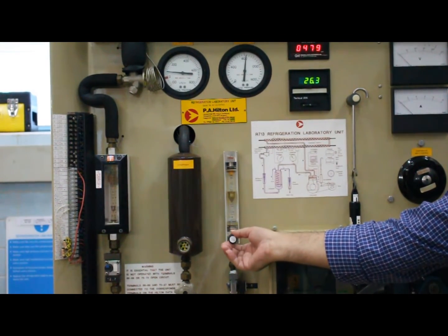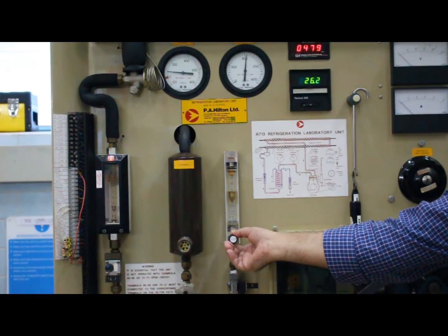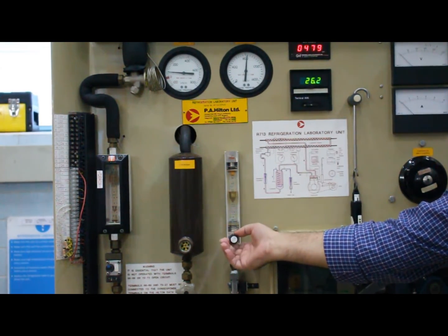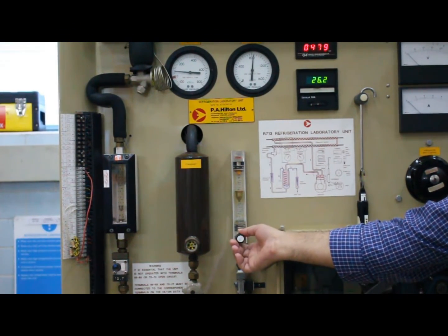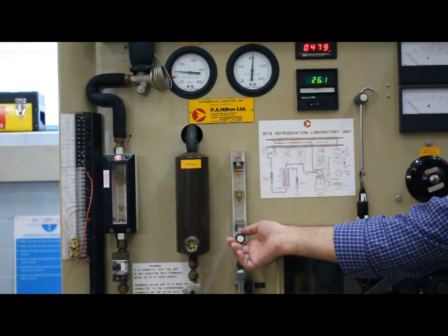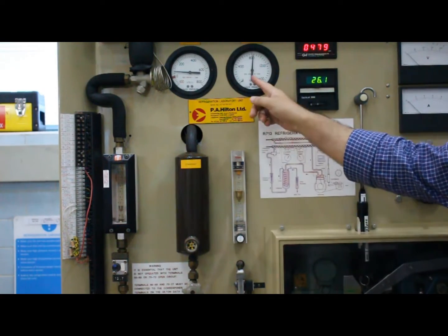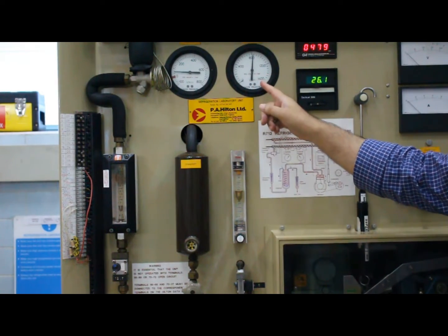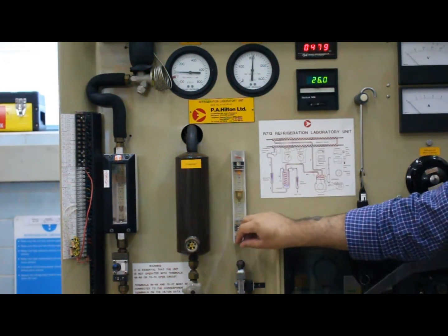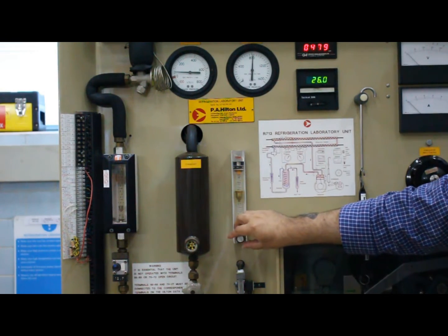So for example, over here there is a spindle attached to this water flow rate. What you can do is rotate it. For example, going towards the left side will actually lower the flow rate. So this needle will be moving towards the higher pressure side. And for example, if you have to set a higher pressure than 800 kilopascal, then you can rotate it on the left side. So this is the maximum flow rate over here.